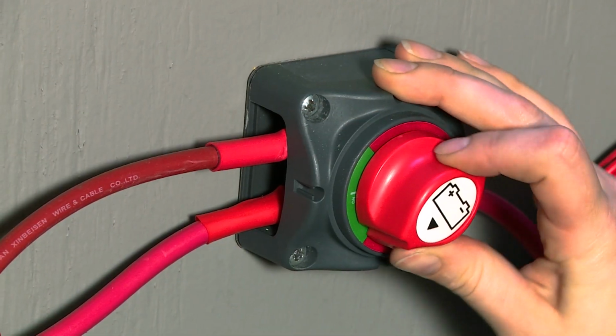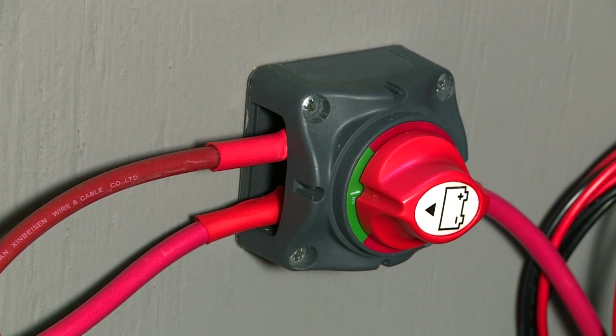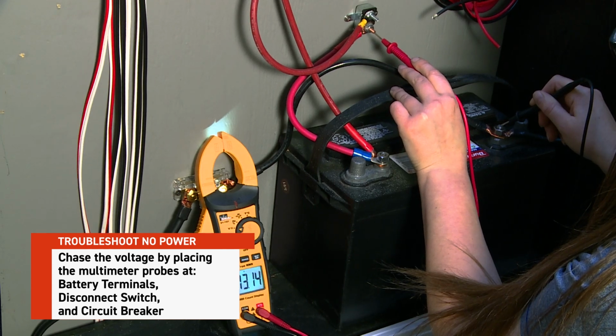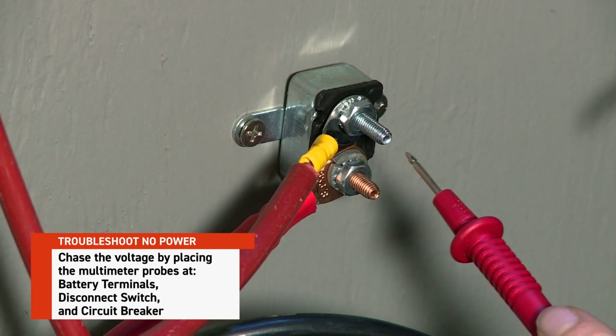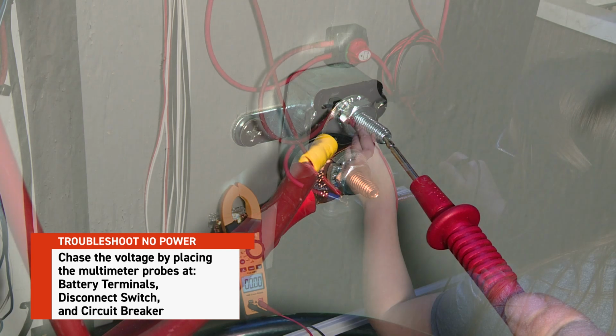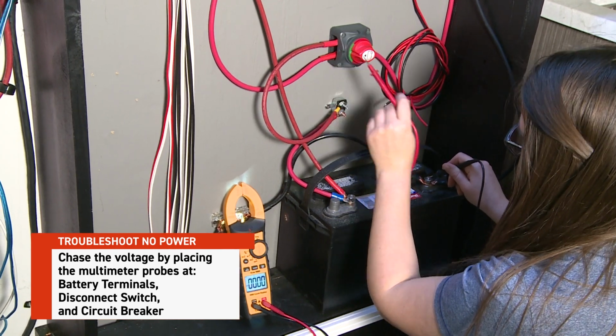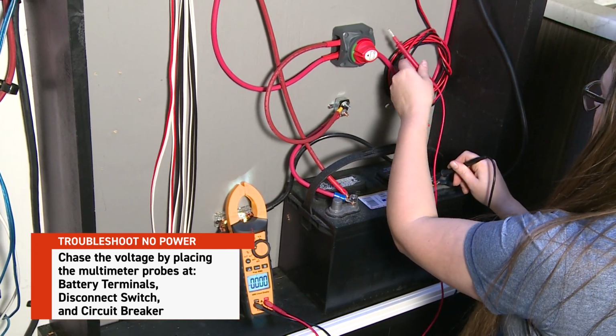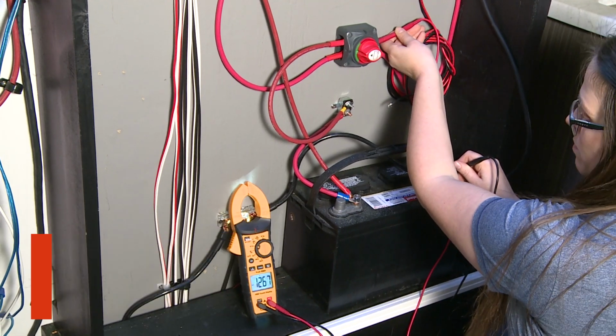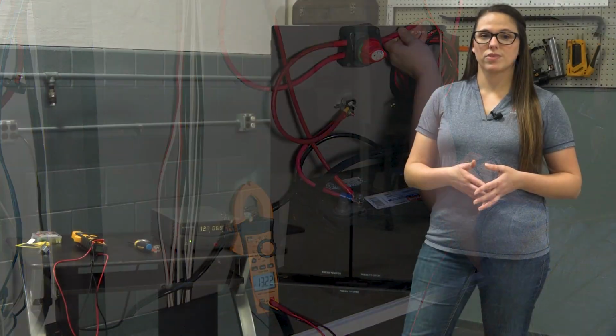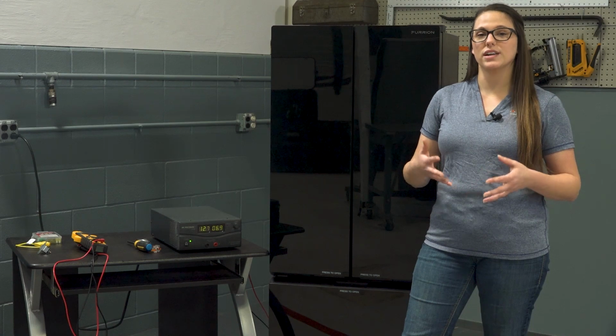Next, inspect the battery components. Confirm the battery disconnect switch is in the correct position to supply power, and check if the main circuit breaker is tripped. We'll chase that voltage, placing the multimeter probes at each component, starting at the battery terminals and moving through the disconnect switch and circuit breaker. If voltage isn't detected at a particular point, that component is the issue and needs attention.